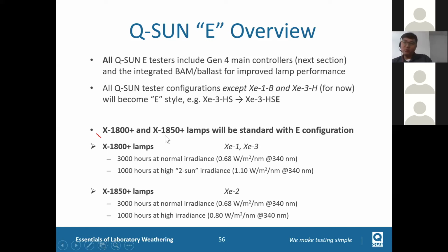What's been improved? In XE1 and XE3, in the past, when testing on daylight Q, with 340 nanometer control, the maximum irradiance setting was 0.68. That could cover 95% of international standards, which typically only require 0.35, 0.51, or 0.55. The maximum for our chamber in the past was 0.68, but right now we can do 1.1, so it's much higher.